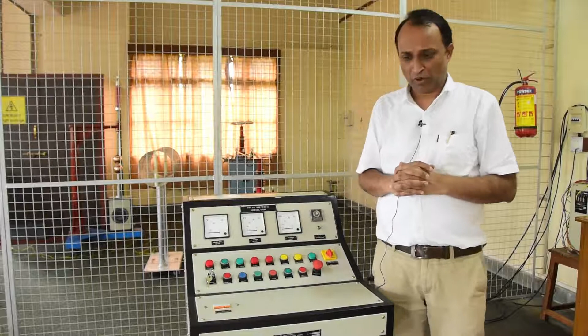In this particular experiment, we are going to observe the corona. There are actually two stages in which corona makes itself apparent in the power system, depending upon the amount of ionization. At the very beginning, when the corona inception starts, there is no apparent visible effect that shows the presence of corona. But as the voltage goes on increasing, a stage is reached where a hissing noise is heard surrounding the conductor even during the steady state condition.